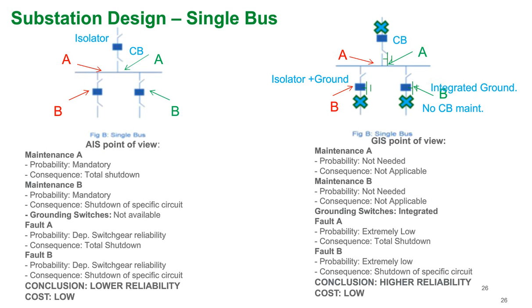Maintenance on air-insulated switchgear is mandatory. We know there is routine maintenance on medium voltage switchgear and metal-clad. Typically when you have maintenance of either the bus bar or the circuit breaker, you're either having a total shutdown of your lineup, or a shutdown of a specific circuit, depending on whether it's a circuit breaker you're doing maintenance on or the bus that you're inspecting and maintaining. In addition, faults depend on the switchgear reliability, so it's different from manufacturer to manufacturer. But the consequence of a fault in the bus bar, of course, is a total shutdown, and the consequence of a fault in a circuit breaker or circuit breaker compartment is a shutdown of a specific circuit.